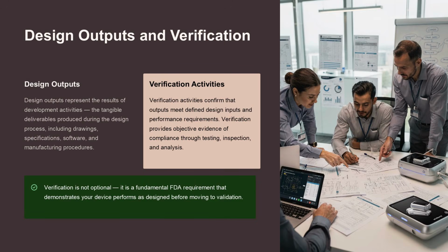Design outputs represent the results of development activities, the tangible deliverables produced during the design process, including drawings, specifications, software, and manufacturing procedures. Verification activities confirm that design outputs meet defined design inputs and performance requirements. Verification provides objective evidence of compliance through testing, inspection, and analysis. Verification is not optional. It is a fundamental FDA requirement that demonstrates your device performs as designed before moving to validation.